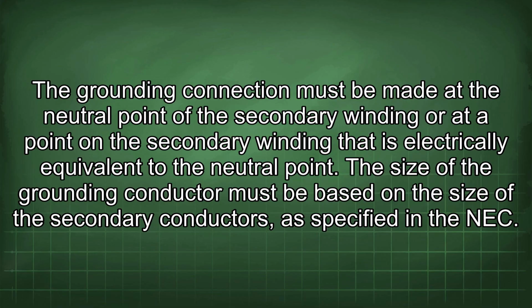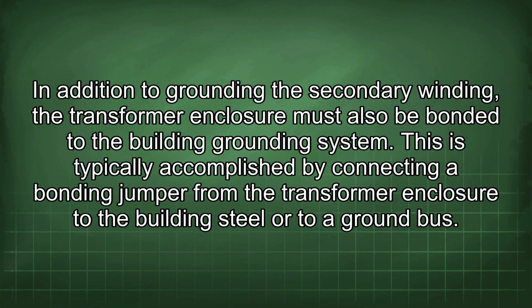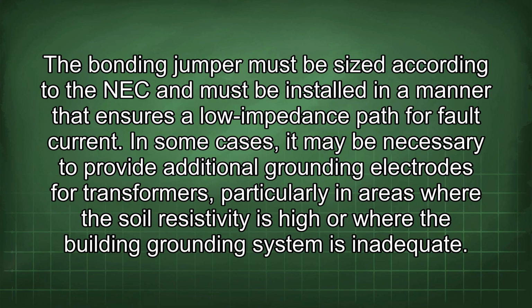The size of the grounding conductor must be based on the size of the secondary conductors, as specified in the NEC. In addition to grounding the secondary winding, the transformer enclosure must also be bonded to the building grounding system. This is typically accomplished by connecting a bonding jumper from the transformer enclosure to the building steel or to ground bus. The bonding jumper must be sized according to the NEC and must be installed in a manner that ensures a low impedance path for fault current.